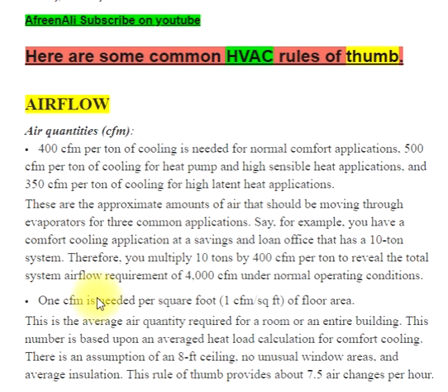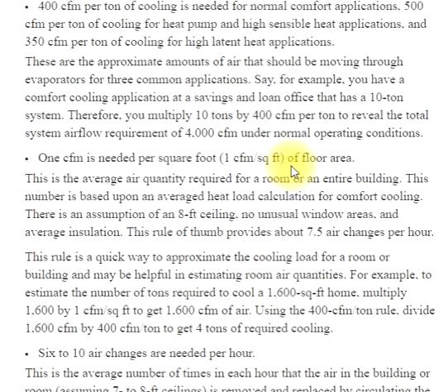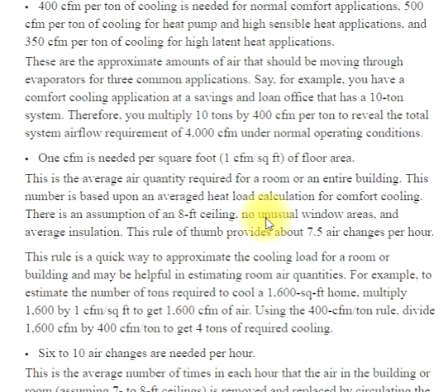1 CFM is needed per square foot of floor area. This is the average air quantity required for a room or an entire building. This number is based upon an averaged heat load calculation for comfort cooling. There is an assumption of an 8-foot ceiling, no unusual window areas, and average insulation. This rule of thumb provides about 7.5 air changes per hour and is a quick way to approximate the cooling load for a room or building.